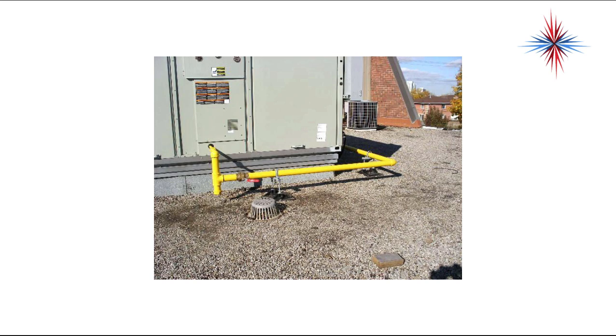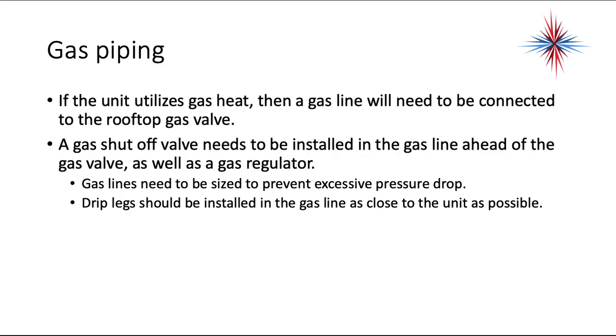And now there's one other thing. Drip legs cannot be installed on the roof if you have a cold environment that's going to freeze. They get installed inside the building. The reason for that is drip legs accumulate moisture, and if it freezes, it's going to break the gas line. So again, for drip legs, check with local code and building officials. There again, if it's in a cold environment or any environment that has a chance of freezing, they need to be installed inside the building.